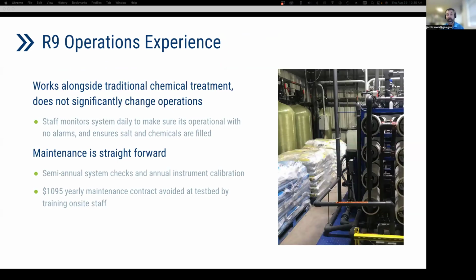As far as the day-to-day operations, you never want to say just plug and play and walk away, but with these, they kind of self-regulate and maintain themselves. We have had to alter our O&M contract a little bit just to make sure we're doing our daily checks, walking around the equipment, checking for leaks, alarms. With the water softening system, you have to add salt on a monthly basis.